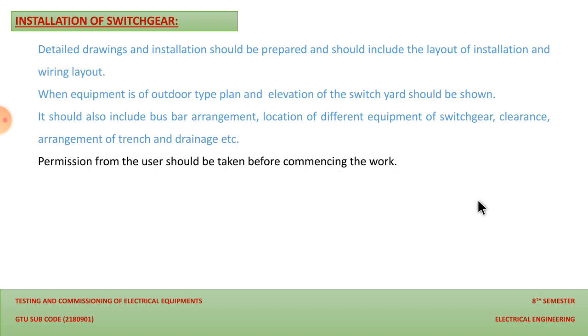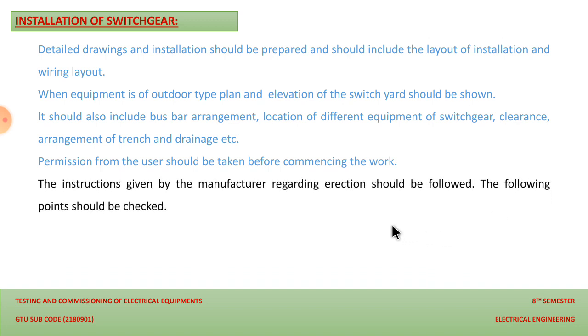So yes, this is again a most important point. While we are commencing any work with our switchgear, we should take prior permission from the manufacturer or the person who is handling this instrument. And the instructions given by the manufacturer regarding erection should be followed. Once you receive your product at your premises, we perform the erection of the instrument. The manufacturer should provide the instructions related to the erection, and the person who is installing the switchgear has to follow all the instructions listed by the manufacturer.